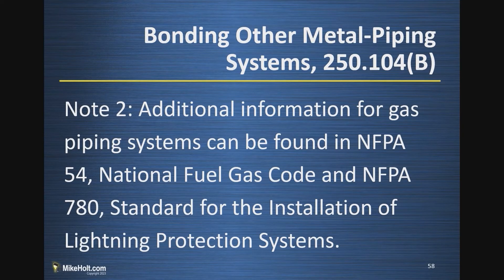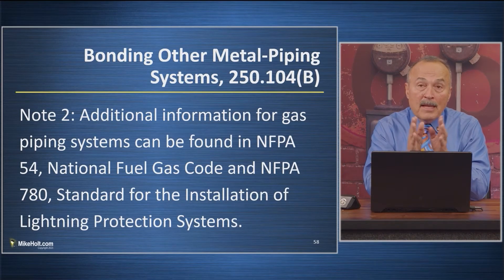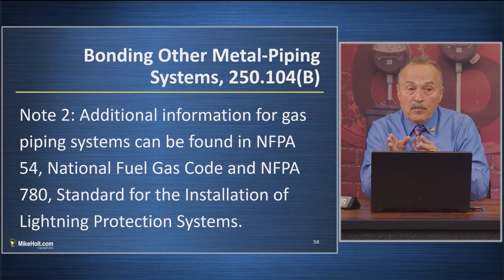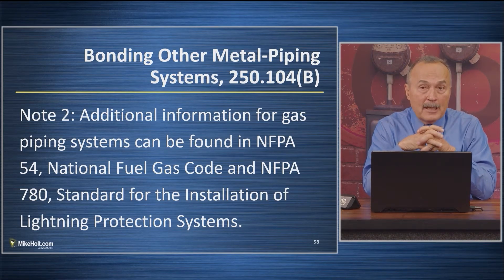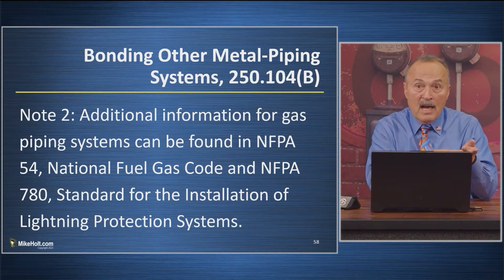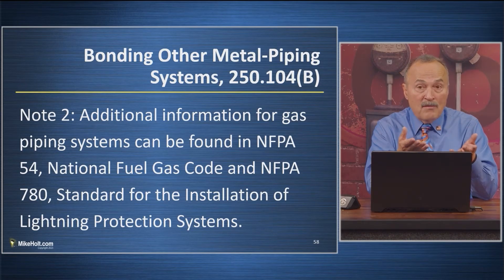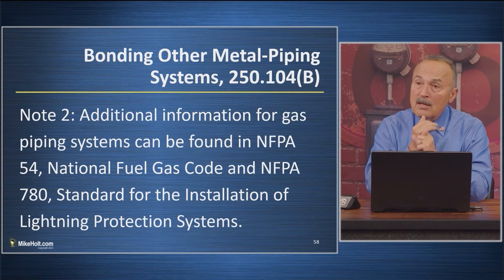NFPA 54, the National Fuel Code, tells you what you have to do with gas pipe bonding. The National Electrical Code does not have any requirements at all having to do with gas pipe bonding. If you go to NFPA 54, it says you have to bond gas piping in accordance with NFPA 70. But NFPA 70 says if the circuit that can energize it contains an equipment grounding conductor, that serves the bonding purpose — which means we do nothing.